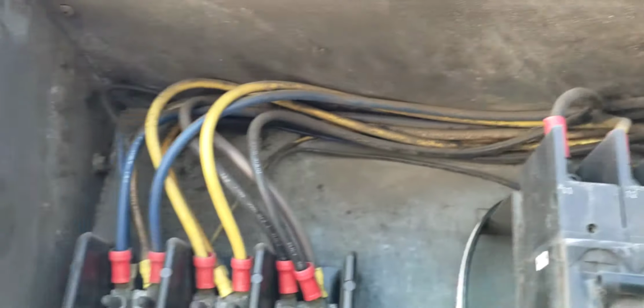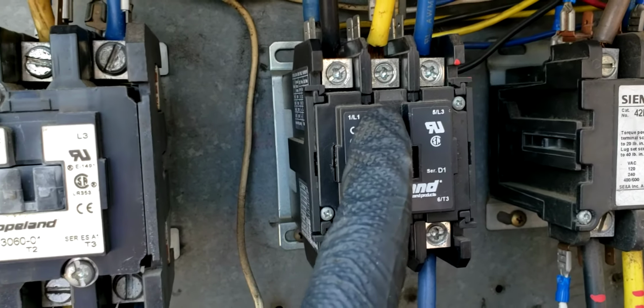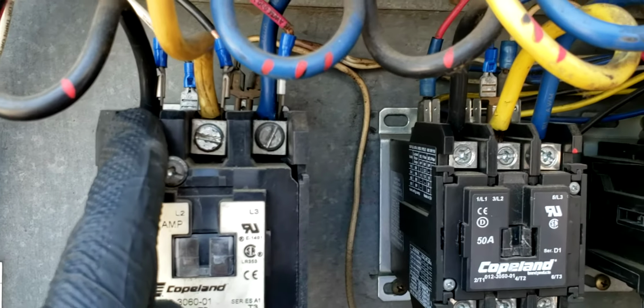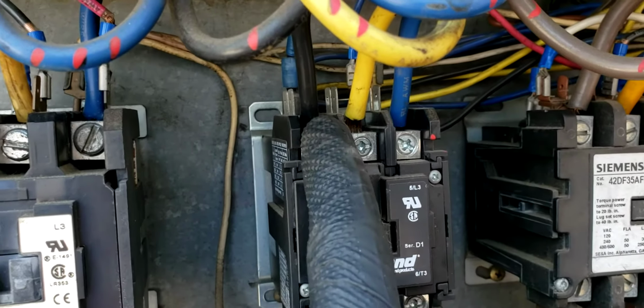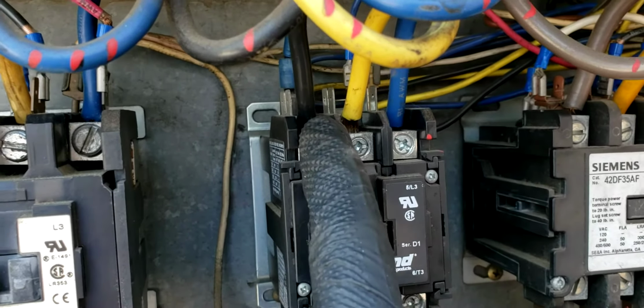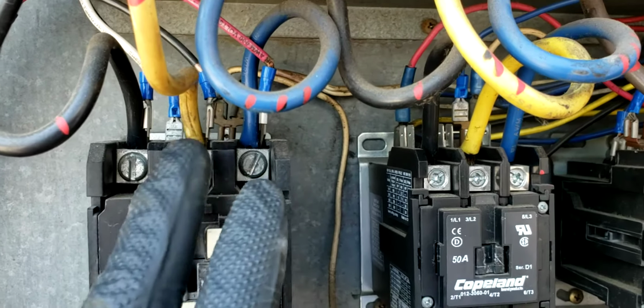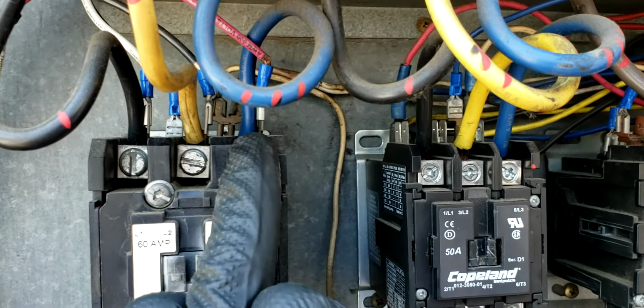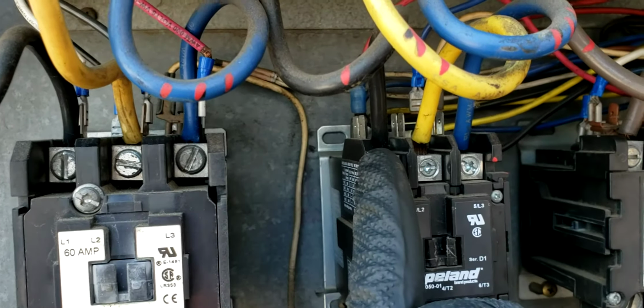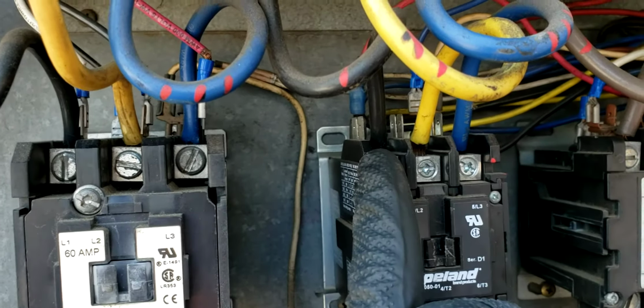Then let's say this is contactor number 2. You would have to then parallel line 1 to this terminal here, line 2 to the middle terminal, and line 3 to the outer terminal, just the way everything has to be in uniform. You can't have line 1, line 2, and line 3 here, and then over here you have line 3, line 2, line 1. You're asking for trouble right there.